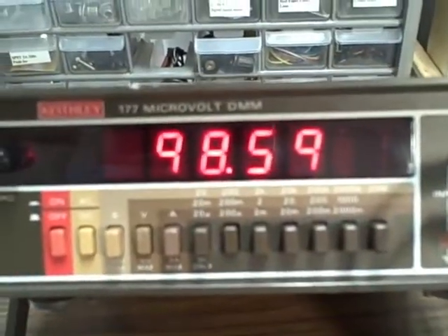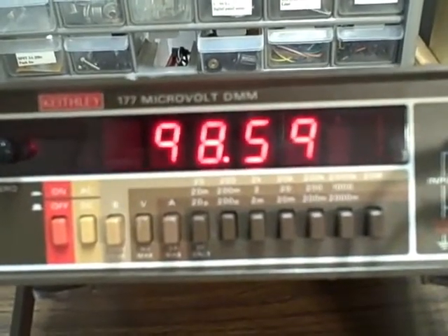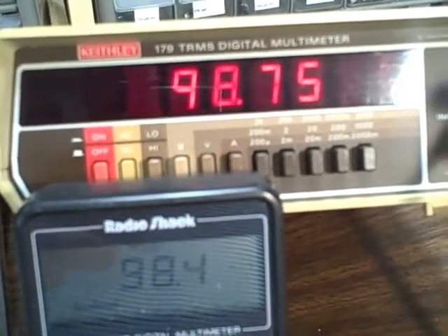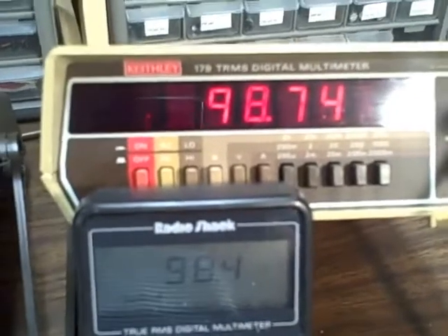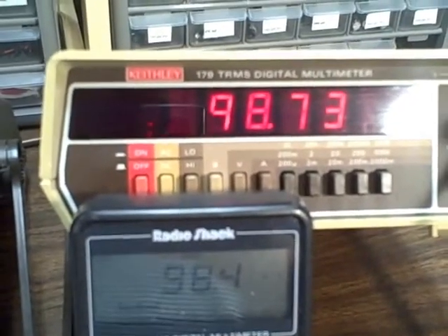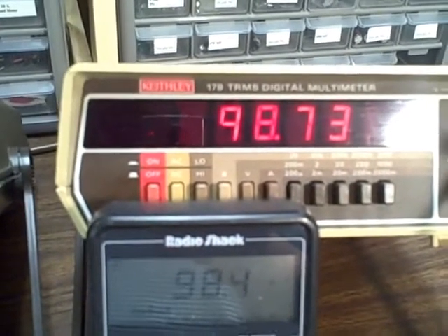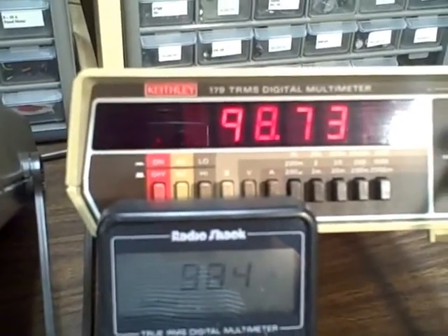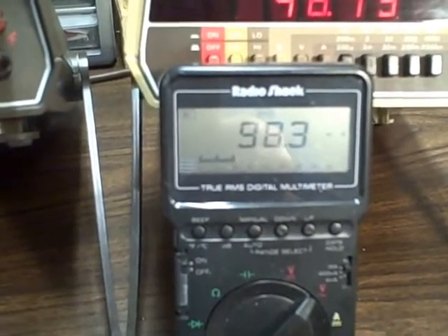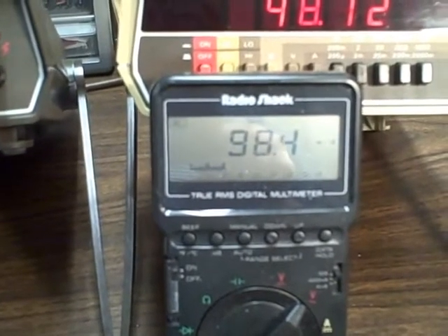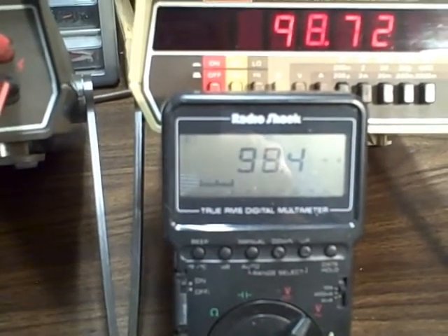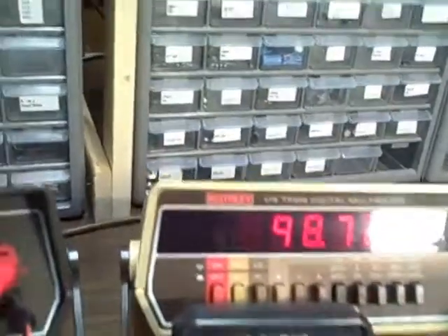And at 200 millivolts, right now I've turned my voltage down a decade up there, so we're reading 98.58 on the 177. We're reading 98.75 on the 179. And this is millivolts now, so we are reading approximately 0.2 of a millivolt different on the 2 meters. And the Radio Shack is reading 98.3 or 4, and that would put it maybe 0.3 millivolts different. So we are within 0.3 millivolts of agreement on all three, and within about 0.2 on the 2 Keithleys.